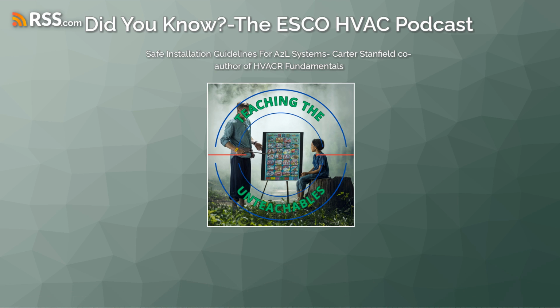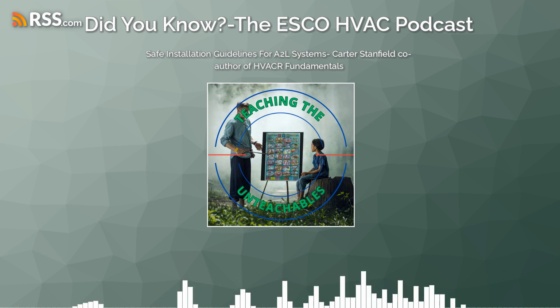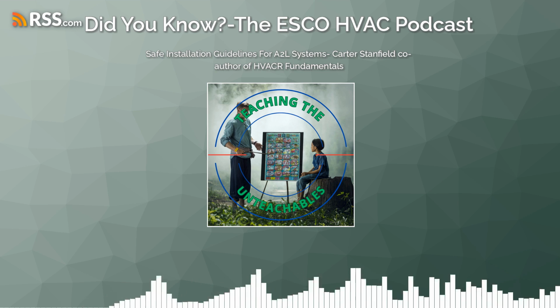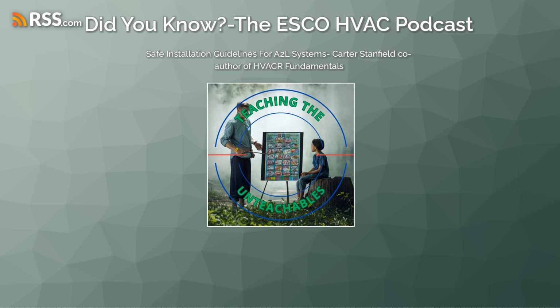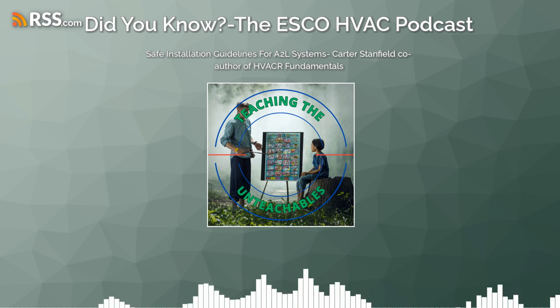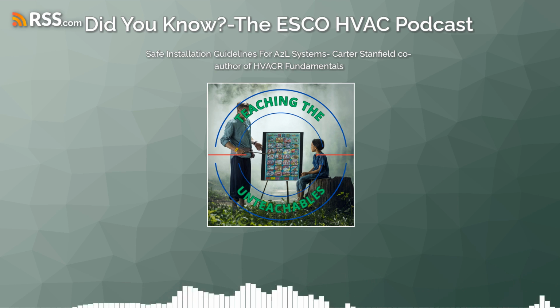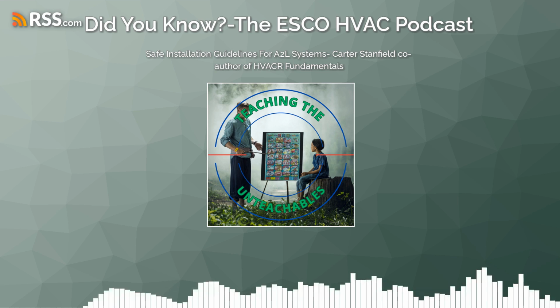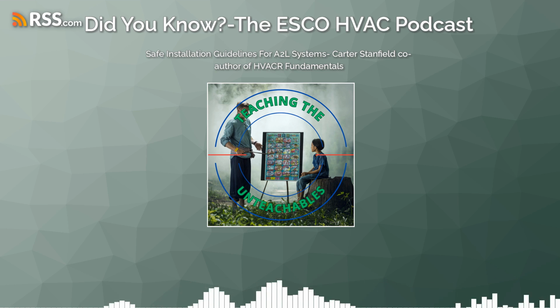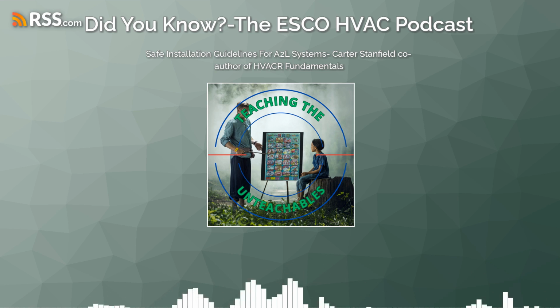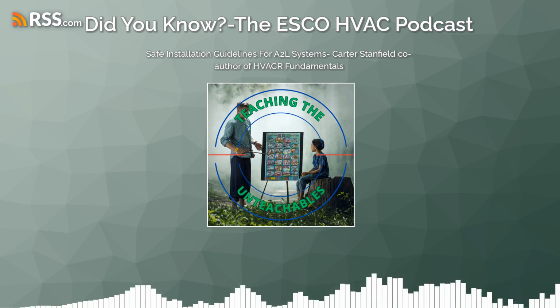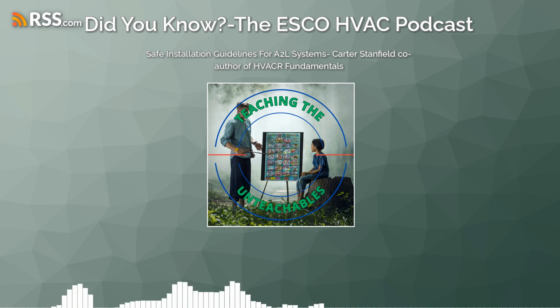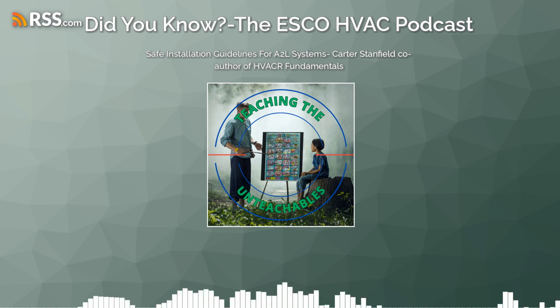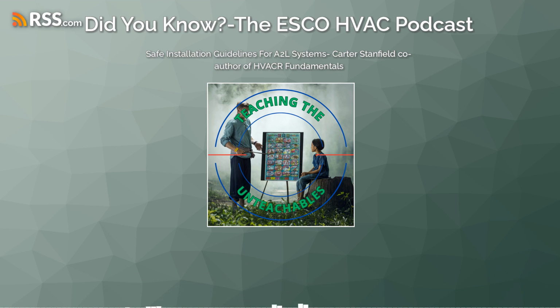The mitigation varies a lot depending on the quantity of refrigerant and also where the system is applied. That's the other thing about Standard 15. The requirements for what you're allowed to do and what you're required to do vary based really on 3 things. The occupancy, that's the building, the refrigerant, and the system, the type of system.